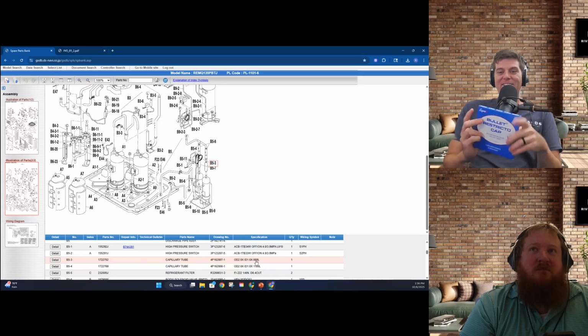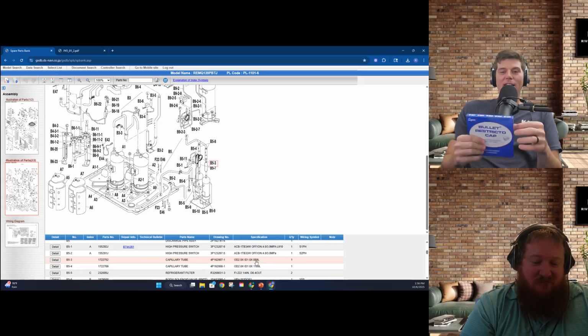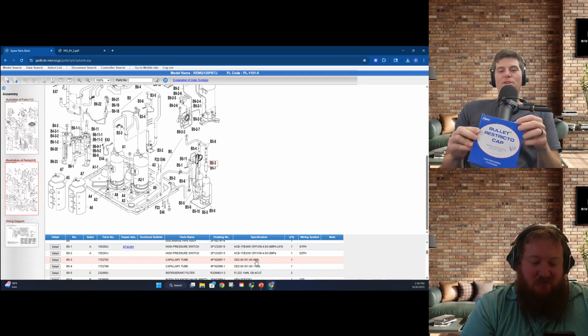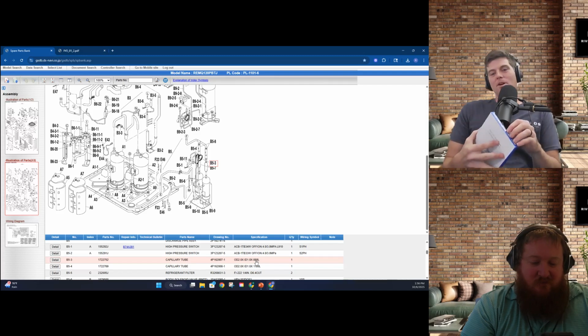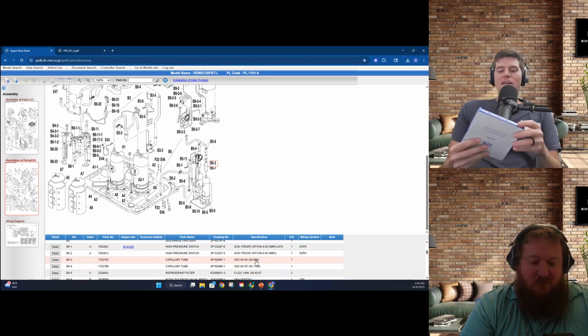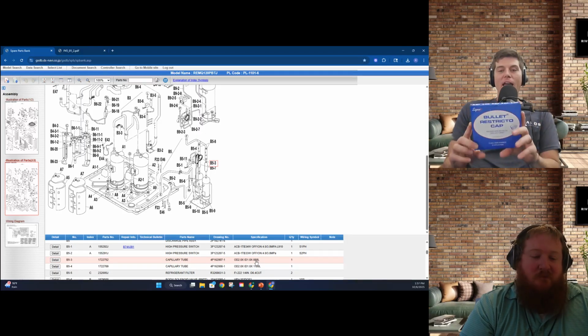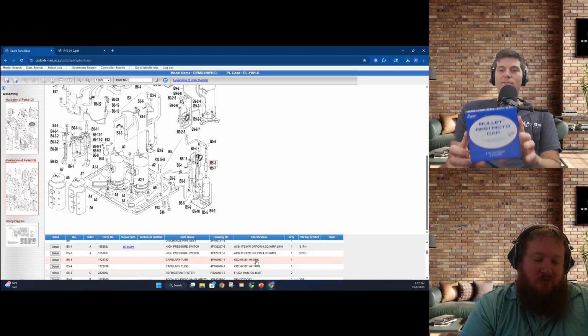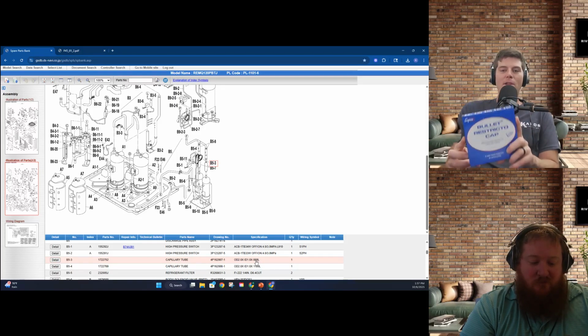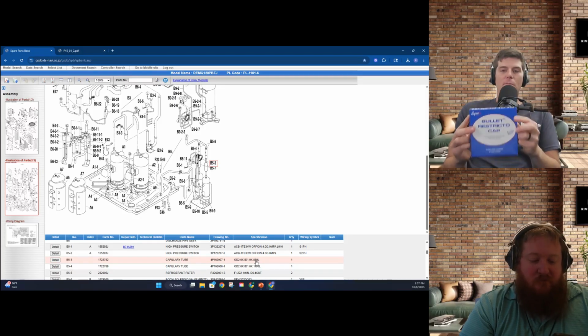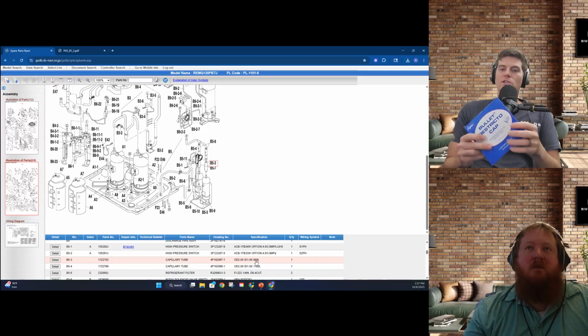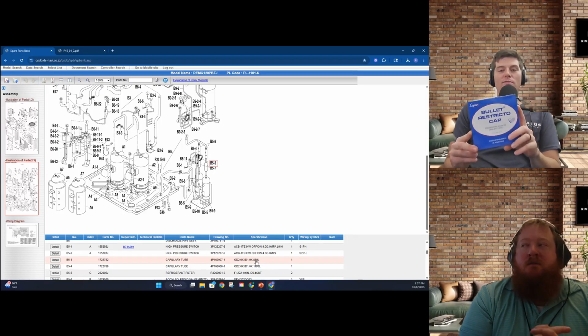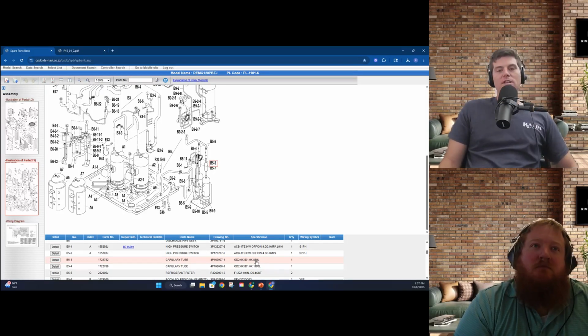Again, if you're waiting for someone to order these parts for you, oh, I can't get them. They can't get them. We can't get them. Come on, stop making excuses and go back to the basics and measure the actual OD, ID, and the length of it, and buy a roll of 50 feet or 10 feet or 20 feet or 6 feet of capillary tubes to make those emergency repairs. Every technician who's running service for Kalos has one of these on their truck. They actually have 2 different ones in 2 different sizes.